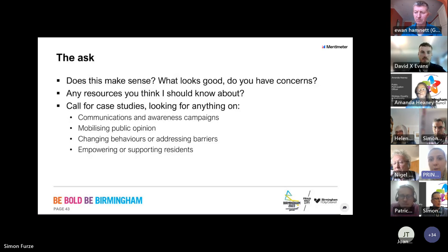But it's also ownership on the secondary side. So we maintain the primary, but we've got a lot of commercial buildings and the heat network efficiency scheme doesn't have much of a successful criteria for commercial buildings. It concentrates on residential, so the success rate of social housing going through will be higher than a lot of commercial buildings. But on the network, we have quite a bit of commercial buildings that are coming back at really high return temperatures. So I think it's something we should capture within the heat network efficiency scheme as well. And yeah, those are my two points.